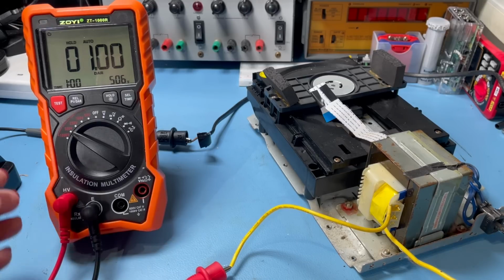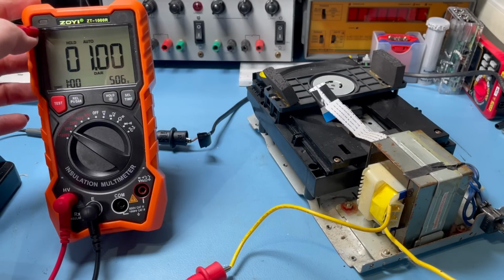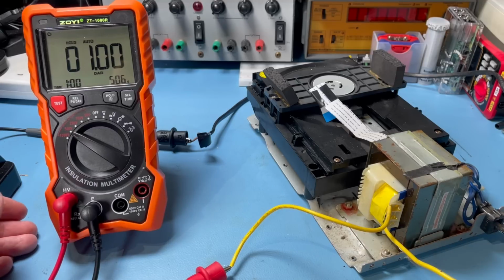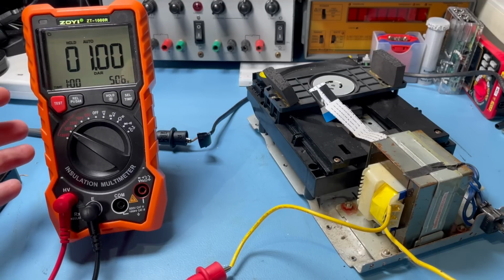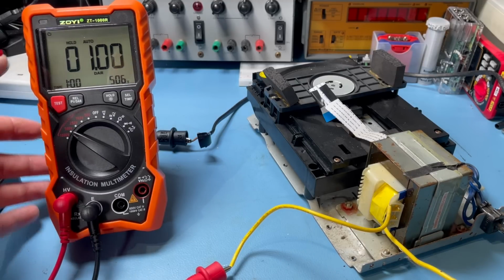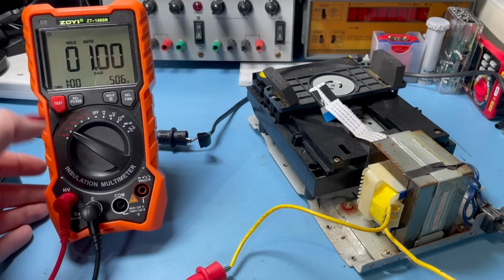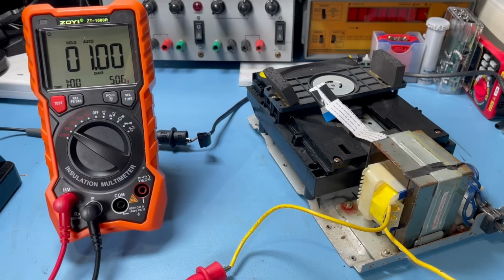There we go. You know, the LED flashed at 15 seconds there to tell us it was taking the first reading, and it compares the resistance values at 15 seconds and 1 minute. We've got a DAR of 1.00, which is fine. They usually tend to be around 1. Anything above 1 is pretty good. Anything below 1 depends how far below 1 it is. It depends on the nature of what you're testing.